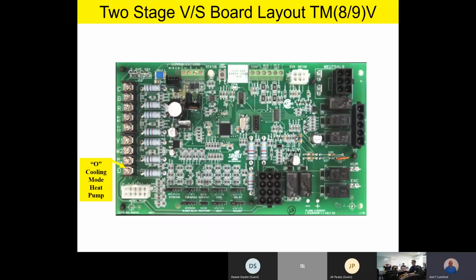Because this is a variable speed product, we also have an O terminal on there. And if you see an O terminal on a furnace product like this, what that automatically tells you is this furnace control is set up or optimized for dual fuel heat pump operation. If you're going to have this on a heat pump outside, you're going to have to move a jumper to tell the board to look for an input on this O terminal.